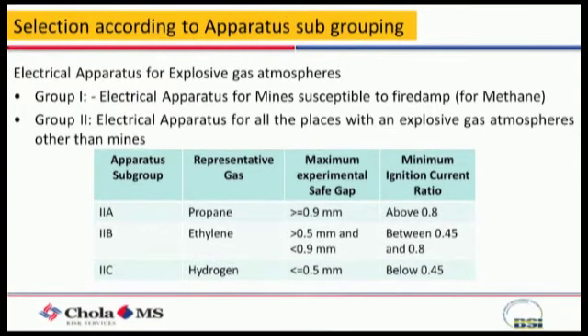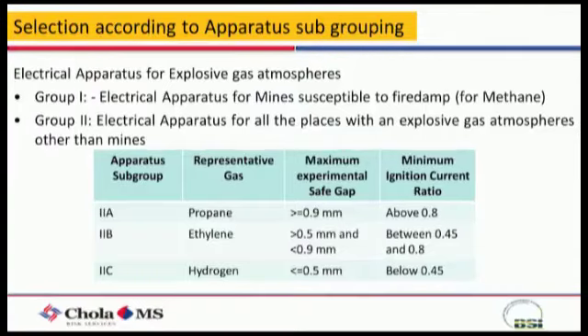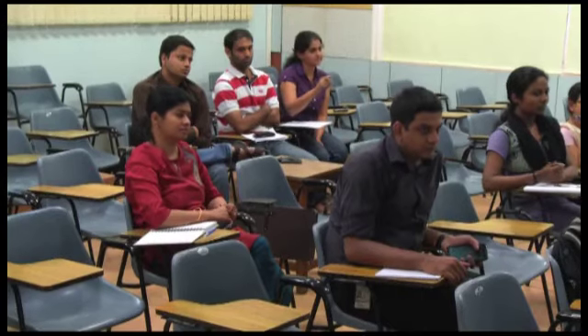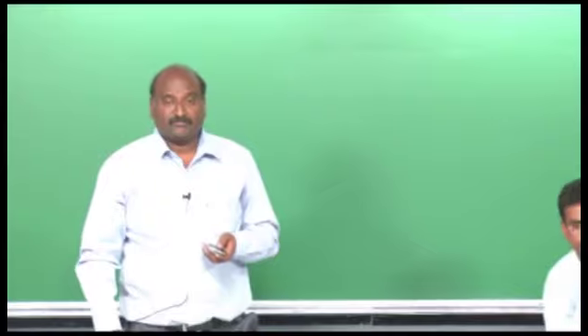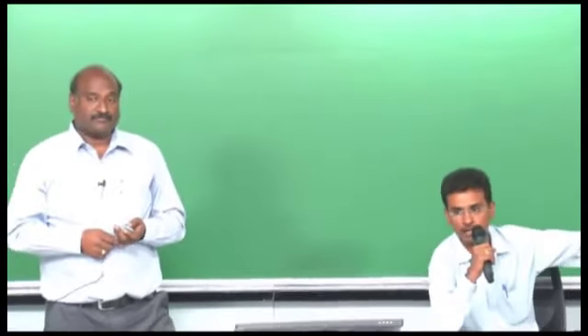What makes you decide that for 2A it is 0.9 and for others it is 0.5 to 0.9? What basically decides the gap? Is it the nature of expansion of the gases present, or how hazardous it is and its molecule size? It's altogether a design by itself. For each and every gas, based on the values MESG and MIC ratio, minimum ignition current ratio, there is a value available.